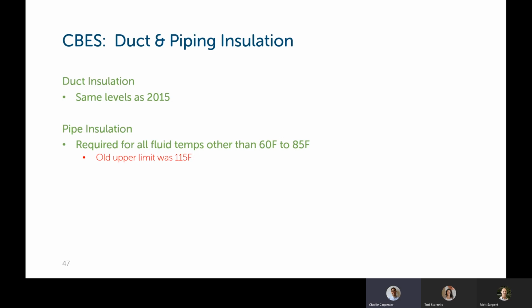Next slide. Duct insulation levels are the same as the 2015 code. That hasn't changed. I do not have them in here, but they'll be the same. For pipe insulation, it is required, whether it's hot or cold water that's being supplied through the pipes, for any temperatures outside of the temperature range 60 degrees Fahrenheit and 85 degrees Fahrenheit. And this is an update. The old limit was 60 degrees to 150 degrees, 115 degrees. Within there, you did not need pipe insulation. They've brought that high limit down a bit. So even just slightly warm water will need some amount of pipe insulation. Next slide.